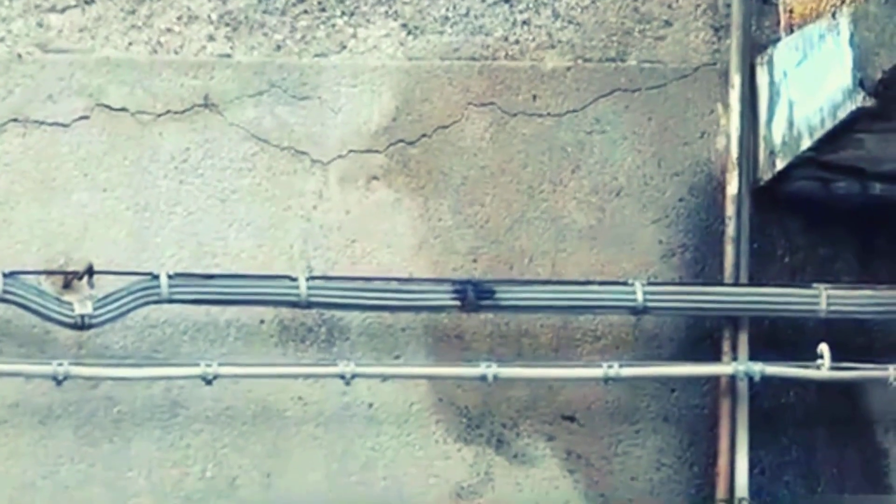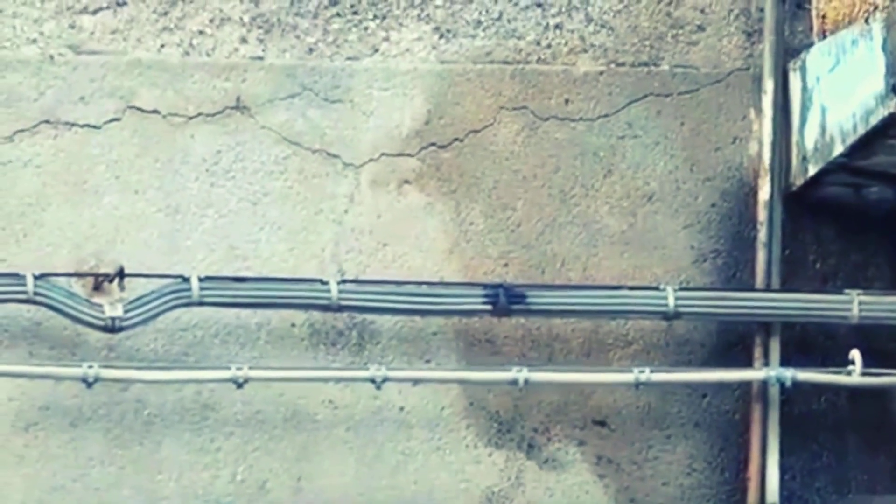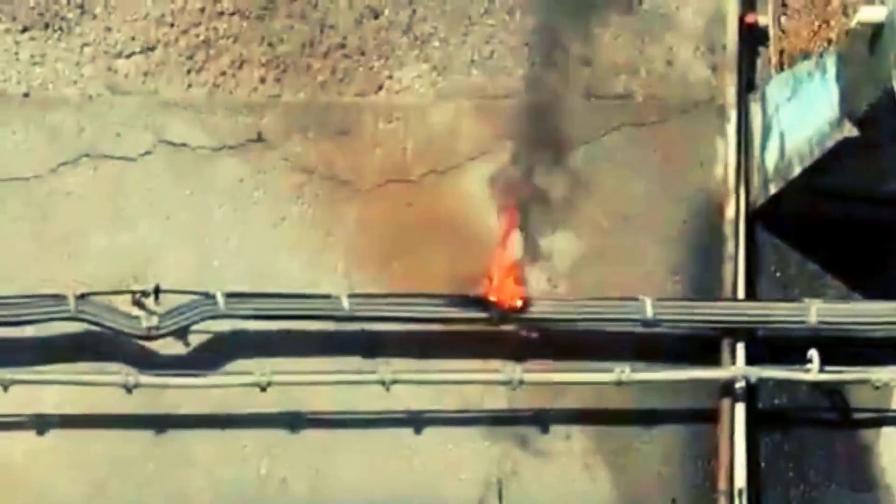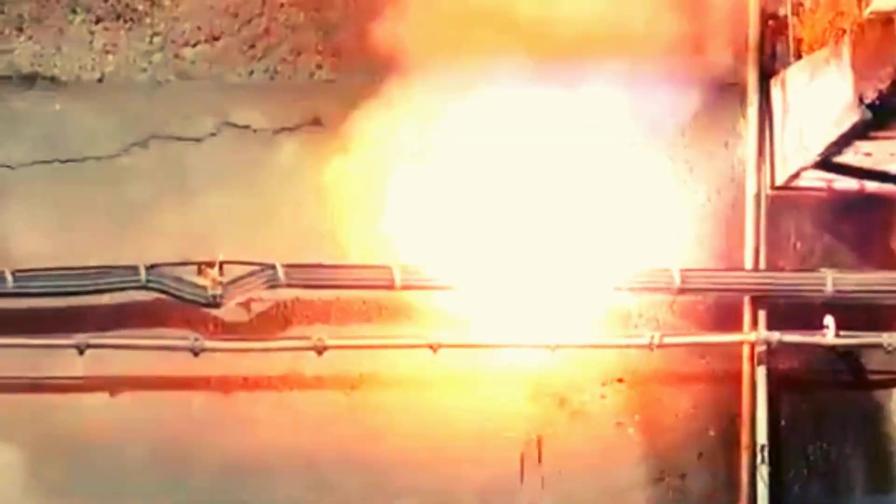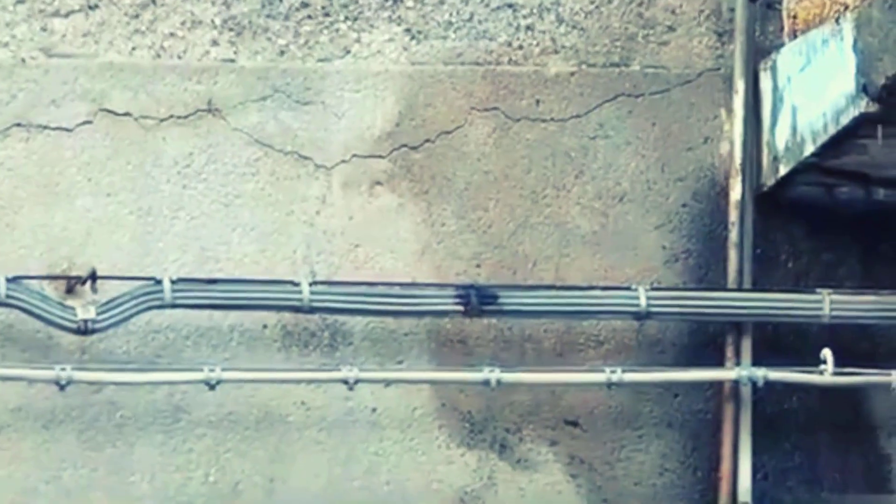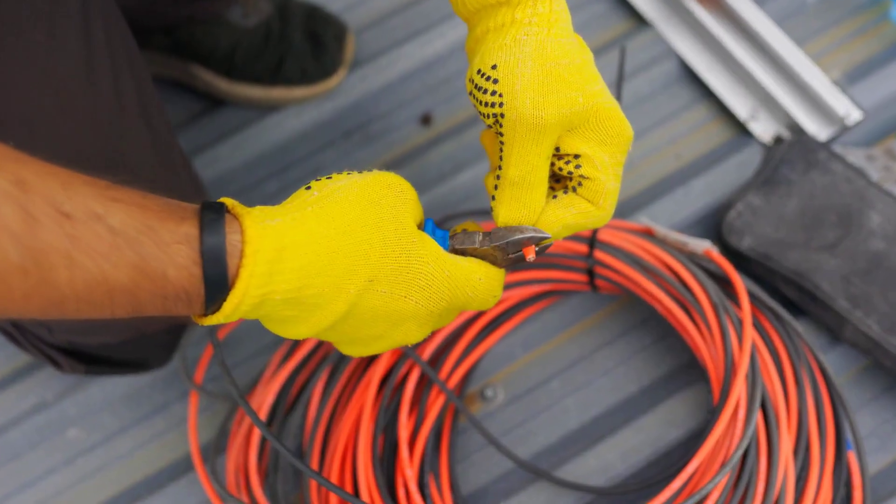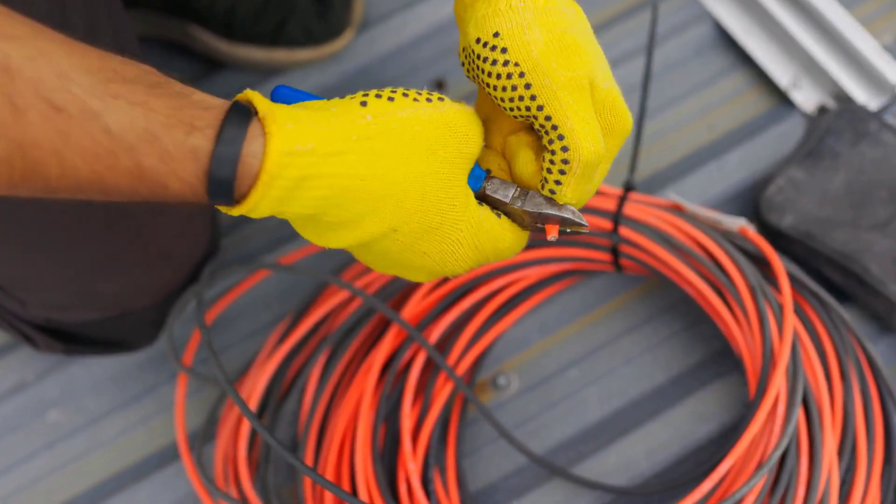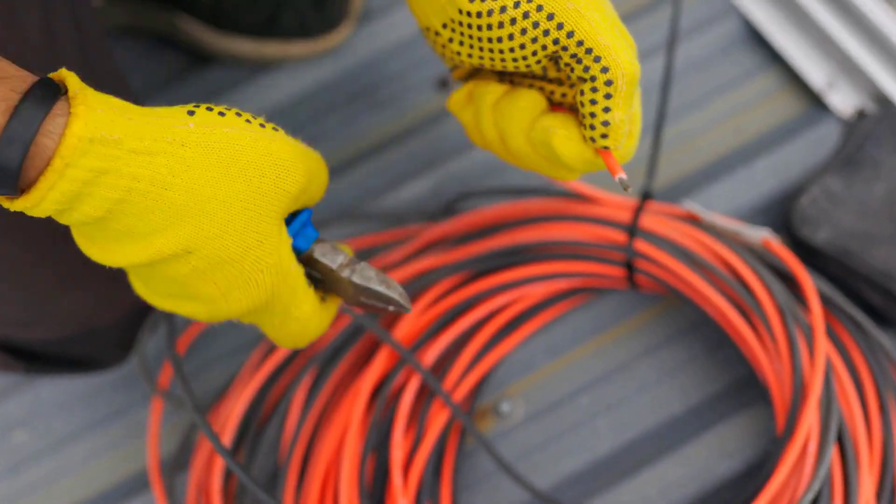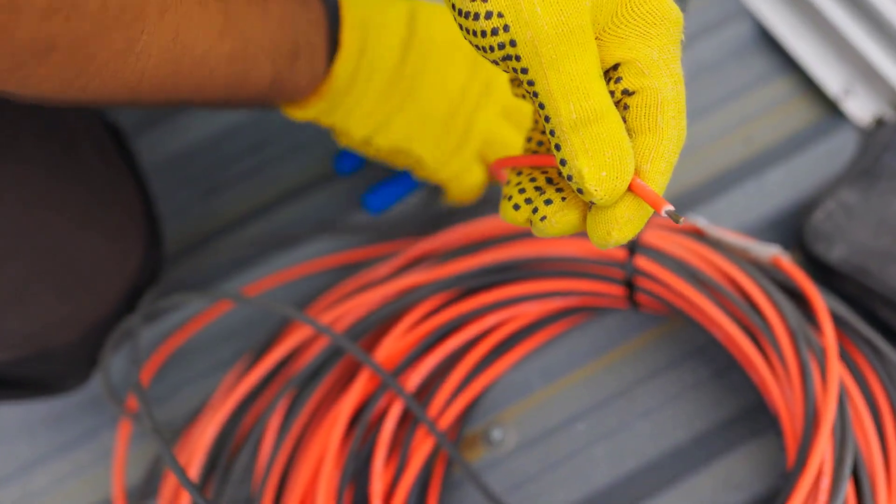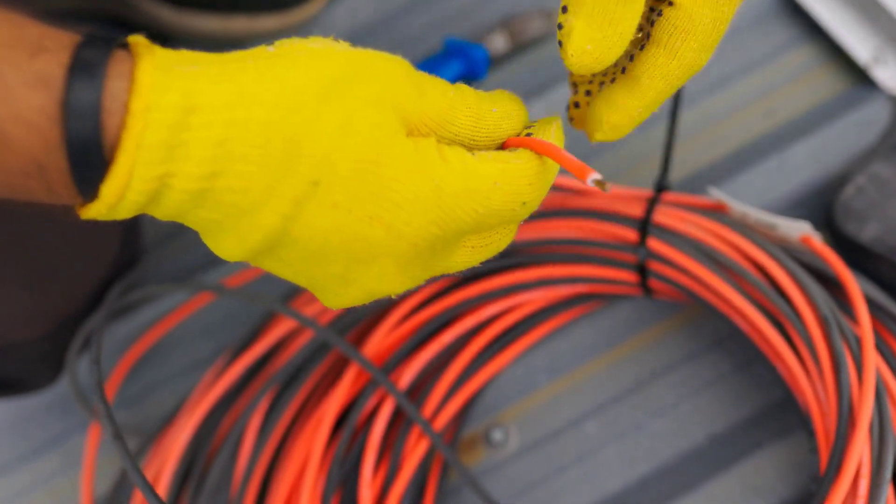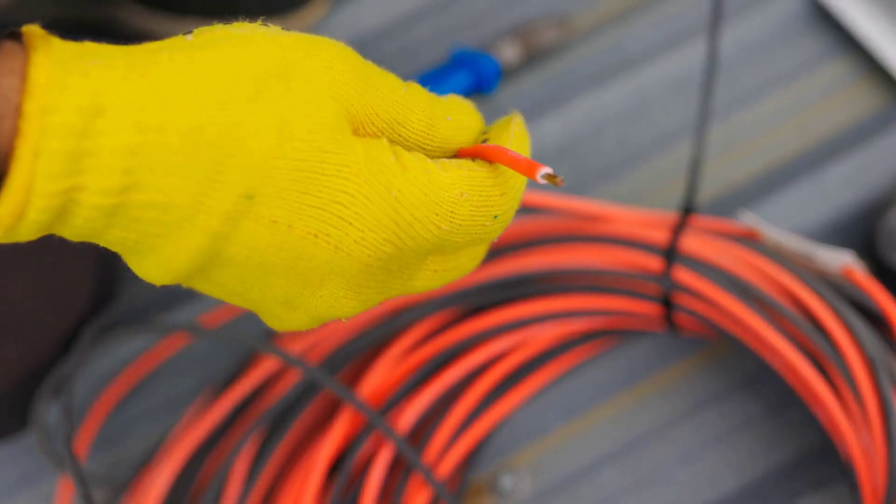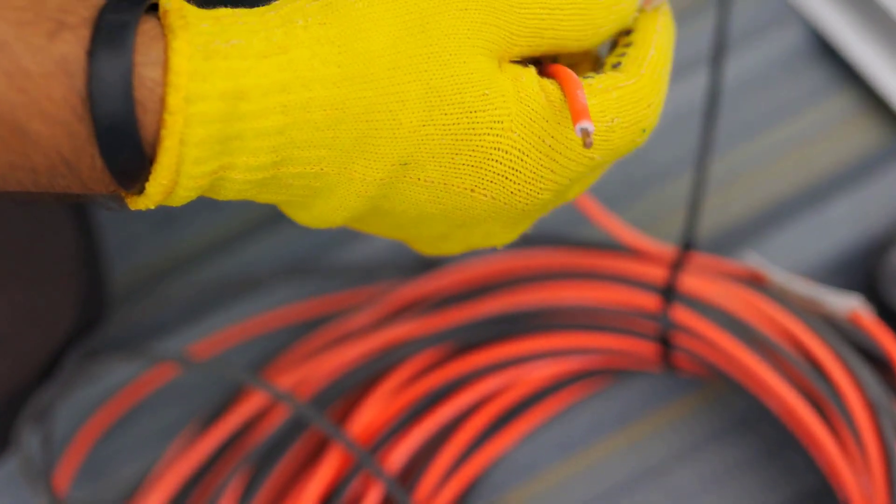Another problem is overheating. When a cable overheats, the insulation material can degrade, causing leakage currents or even a short circuit over time. This brings us to the concept of cable capacity. Cable capacity defines the maximum amount of current a cable can carry without damaging the insulation. This is essential to ensure the longevity and safety of the system.